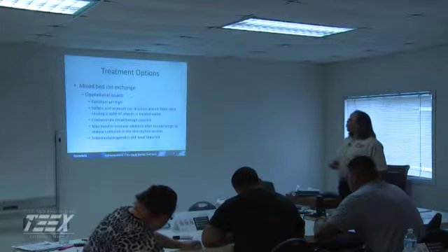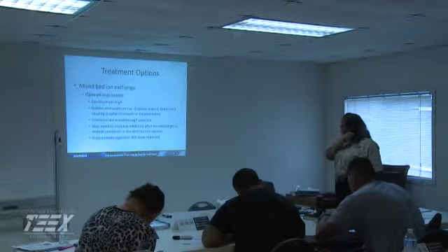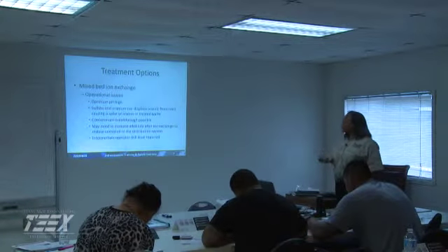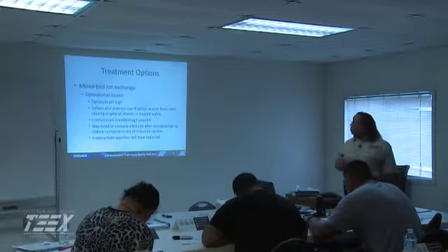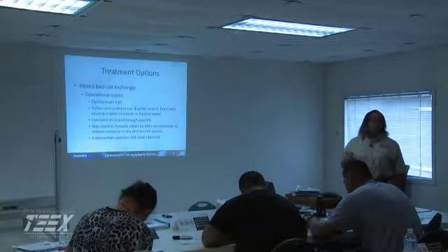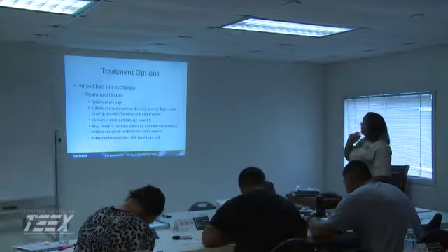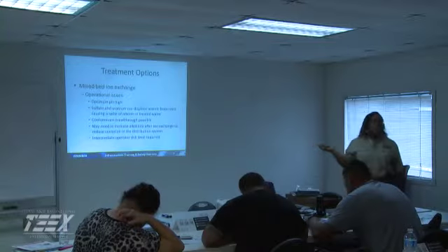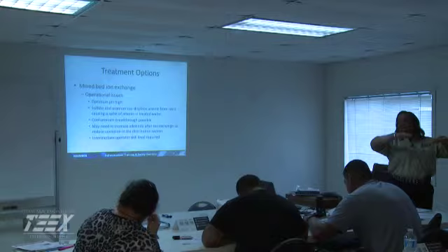All right, we have issues there too. It is pH dependent. It works best at a high pH. Sulfate and uranium can displace arsenic, causing a spike of arsenic in your treated water. Breakthrough, and that's something we never want to happen. And you may need to increase alkalinity. If it works best at a high pH, alkalinity comes into play, because alkalinity is that buffering capacity to maintain a certain pH.